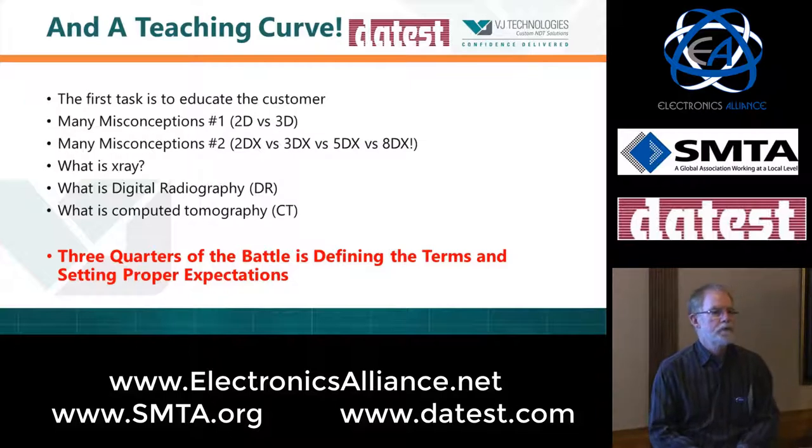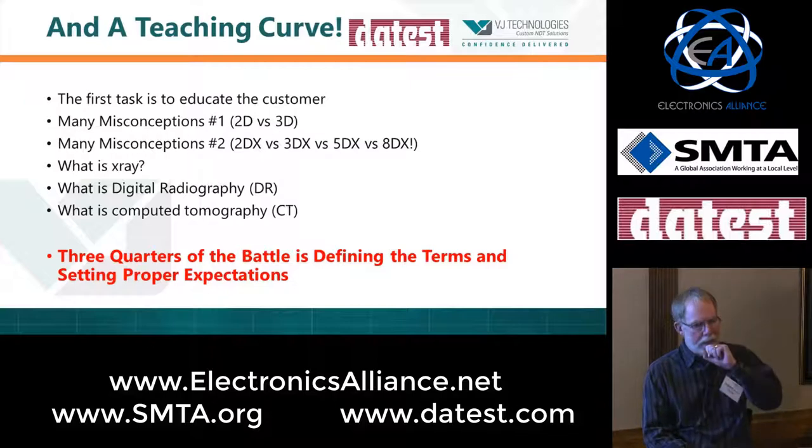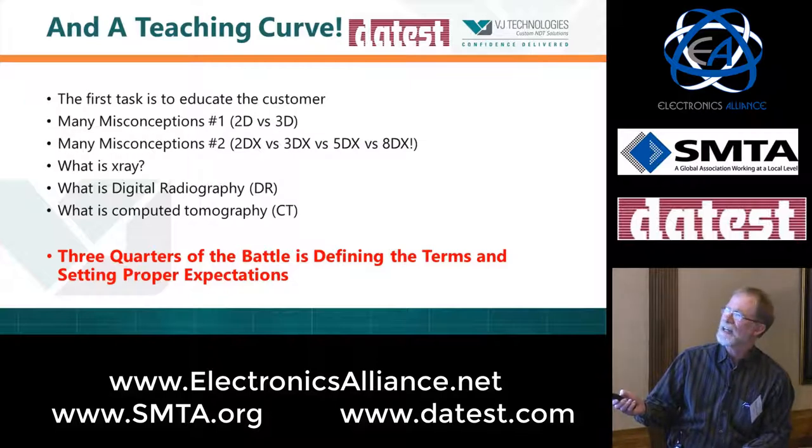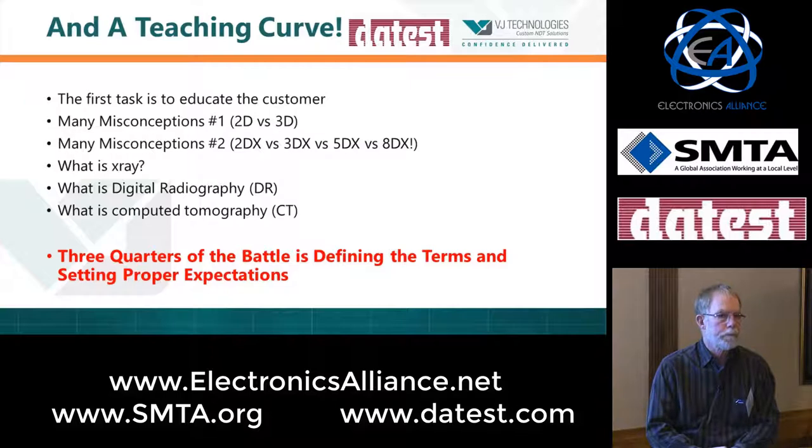5DX is a trade name. That's all it is. It was invented by Hewlett-Packard back in, I think, the early 90s. They inherited a patent from a company called 4Pi in San Diego that developed the technology. It was originally called 3DX for three dimensions. They wanted to market it to the wider world. They wanted to sell it in Asia, so their first thought, new and improved version, we're going to call it 4DX. Well, for those of you who've done business in Asia, you know four is not a very lucky number. So the bright MBA minds at Hewlett-Packard Agilent said, let's make it 5DX, we'll skip over four. And that's the etymology of 5DX. But I still get calls several times a year from people thinking that means dimensions. It doesn't.